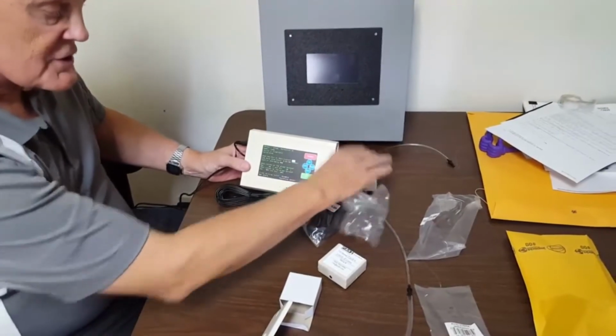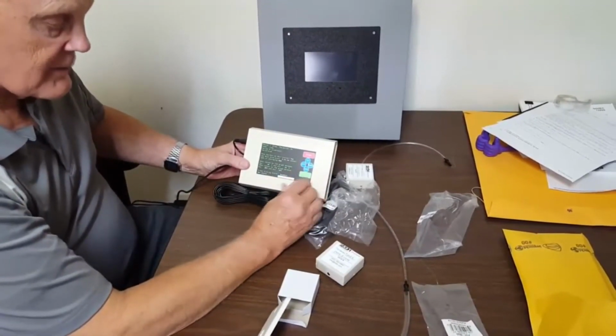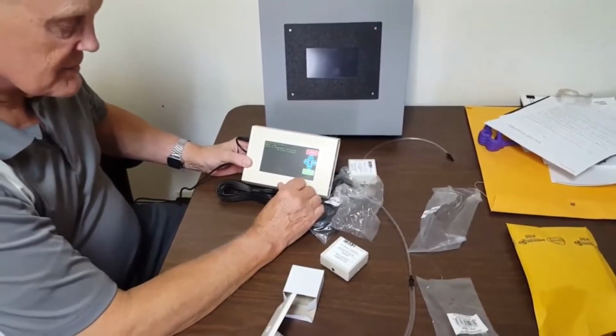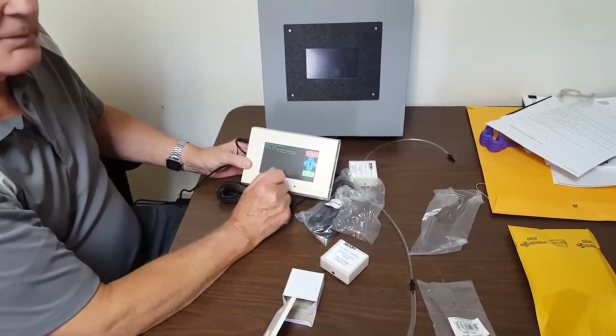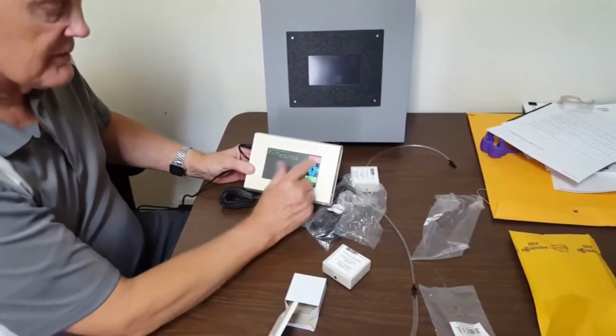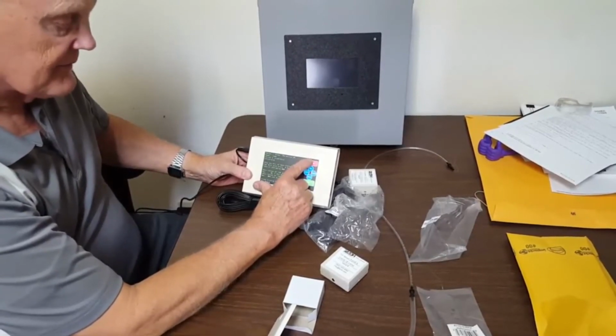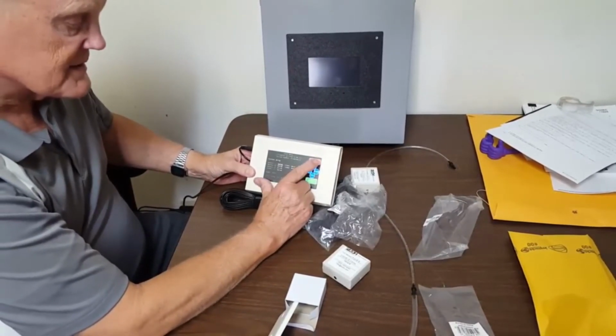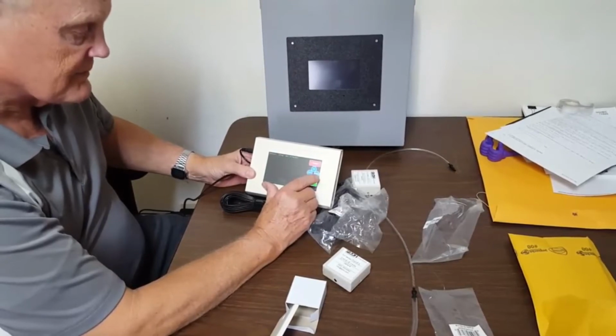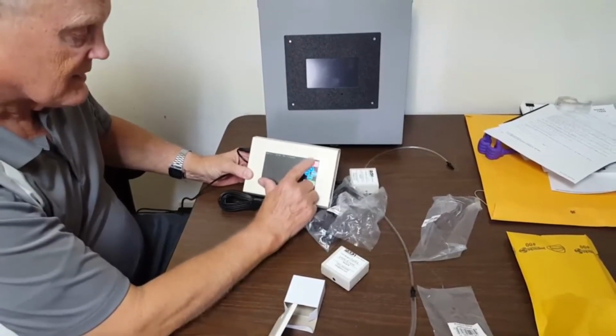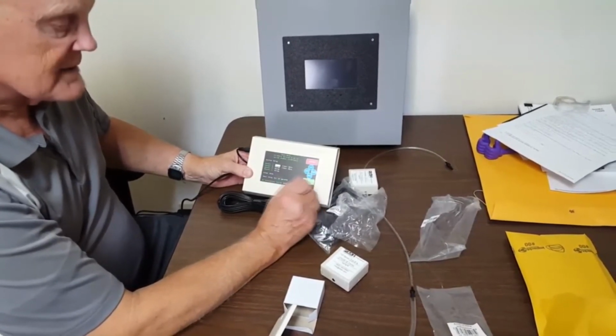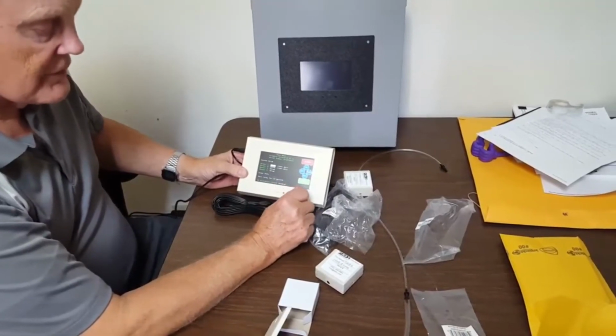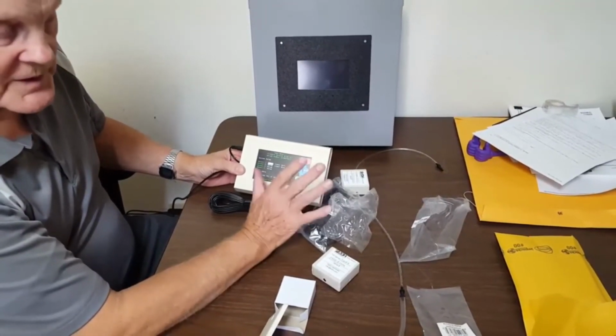Once this is in position, you want to go to the calibration sensor, press plus enter, then select auto calibrate and push the auto calibrate button. This will automatically zero out the sensor so that it reads 0 pressure between the two rooms.